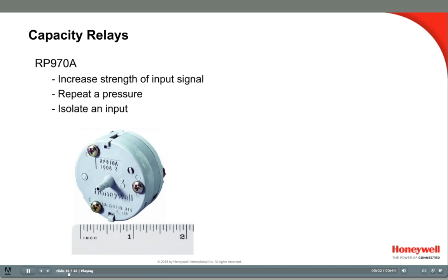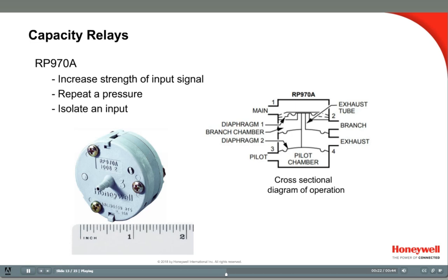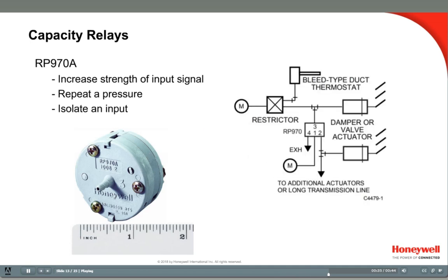The capacity relay has several applications. It's often used to strengthen a signal over a long tubing run, or to assist a controller in filling a large actuator or bank of actuators from a single controller output. This relay can also be used to repeat a signal or to isolate a signal from a pneumatic circuit. Port 3 is connected to the pilot circuit that triggers the relay, port 1 goes to the main air supply, and port 2 is the strengthened relayed signal that goes to the damper or actuator. In this example, port 3 is connected to a branch line from a thermostat, and port 2 is connected to the damper at the end of a long run.